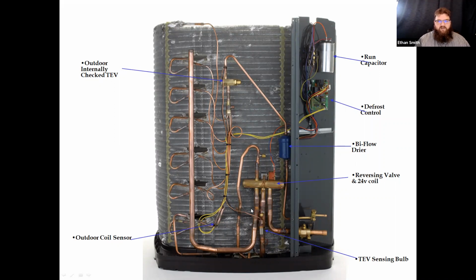We get some extra sensors with this. We get a TXV sensing bulb down here on the true suction line. And you'll notice that we have ports both on the compressor discharge and the true suction line here so that you can get accurate pressure readings regardless of your mode of operation. This particular valve is an internally checked TXV, so we don't have a big check valve that goes around it. It's built into the TXV itself.